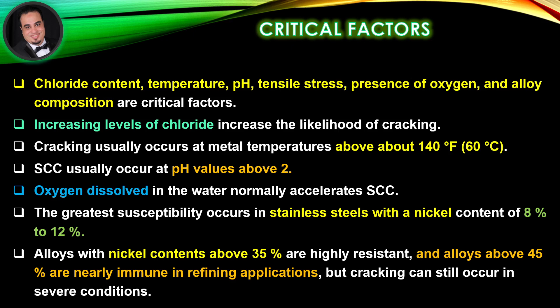Increasing levels of chloride increase the likelihood of cracking. Cracking usually occurs at metal temperatures above about 140 degrees Fahrenheit. Stress corrosion cracking usually occurs at pH values above 2.